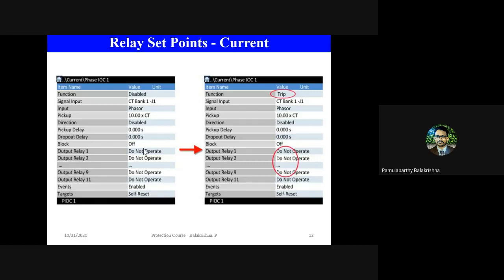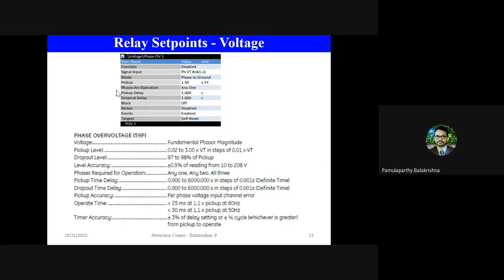Okay, so this is how a practical overcurrent function is configured. Similarly, I am giving just another example of voltage. It will be more or less the same. The other features will be more or less the same. But for voltage, you can see which PT signal it is coming from is mentioned here. Then the mode of voltage, whether I need to use line to ground voltage or line to line voltage, I can mention here. And similar to the current, I can set the pickup. So here, if the voltage reaches 1.5 times the PT ratio, I have to consider this as an overvoltage. Okay. So similarly, I can have delays configured similar to the current I have mentioned earlier.